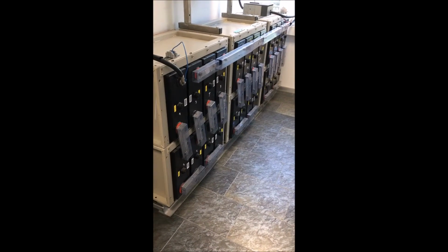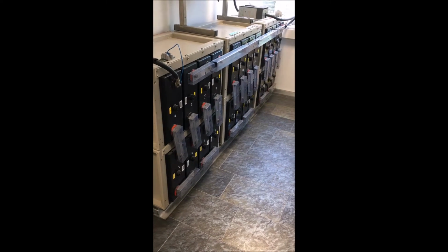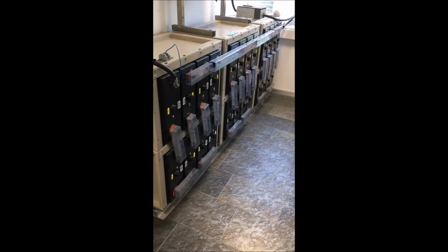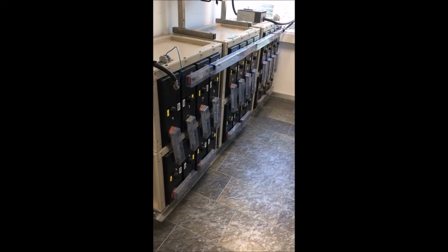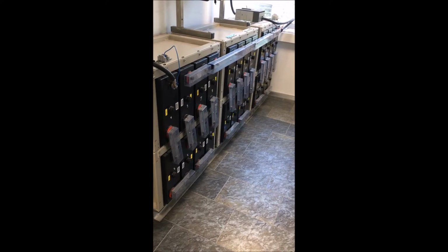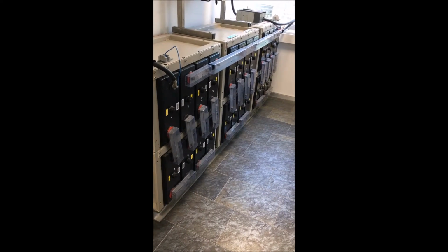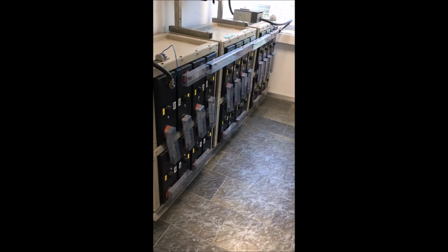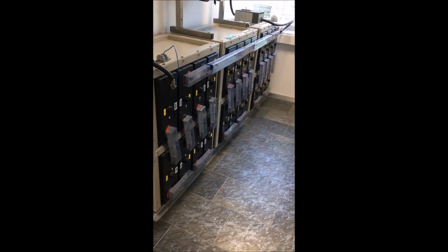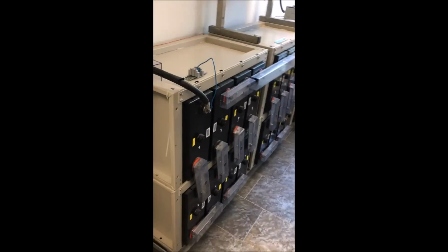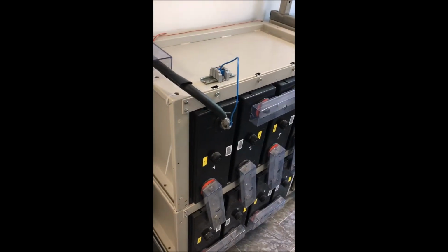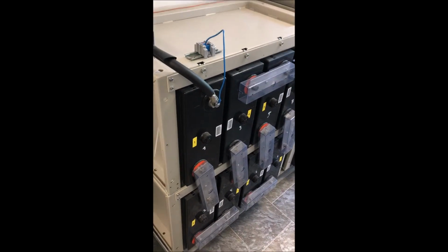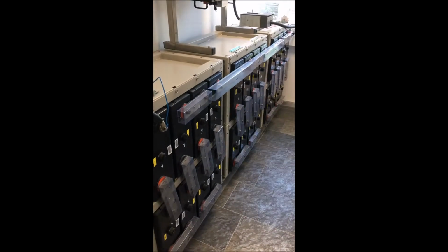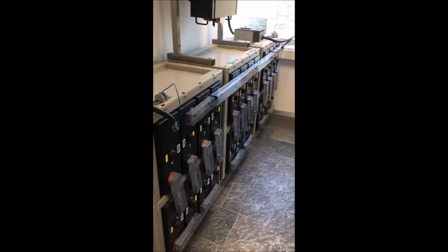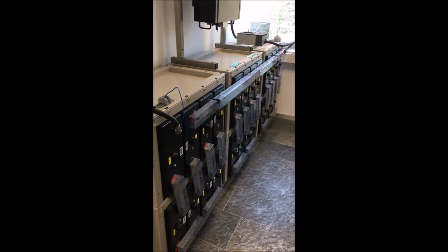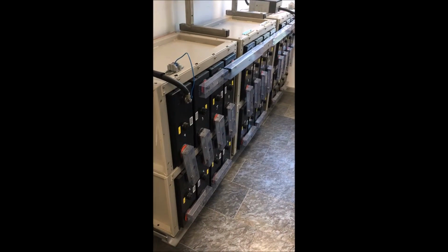The heart of our systems are the Hitachi advanced lead-acid batteries using nanocarbon particles for an enhanced lifetime. These batteries are very compact compared to conventional OPZV batteries. They come in a solid metal frame that can be stacked 4 modules high. This enables us to save installation space and also mount these batteries into standard 20 feet containers.